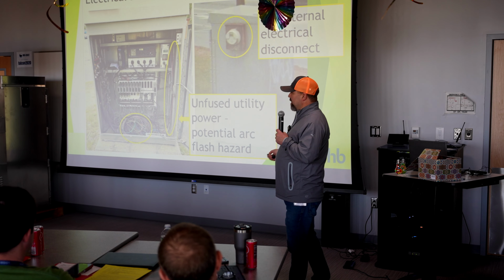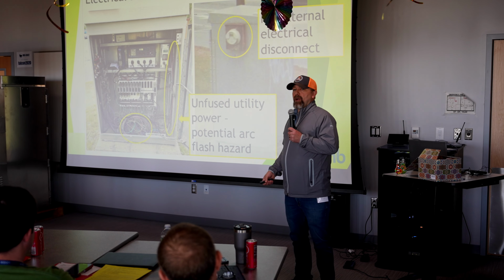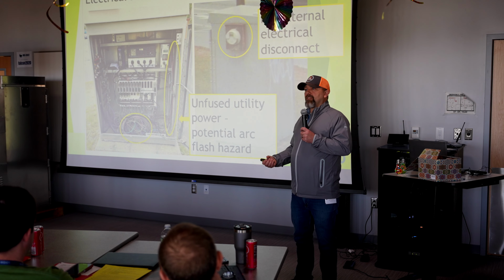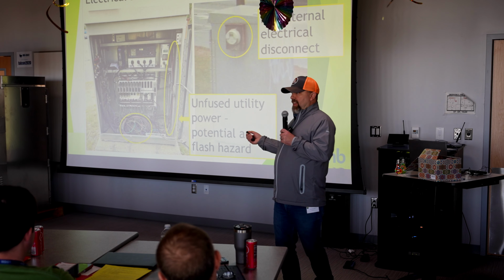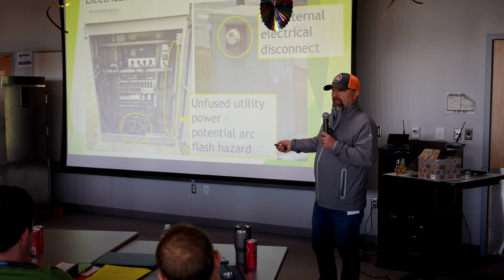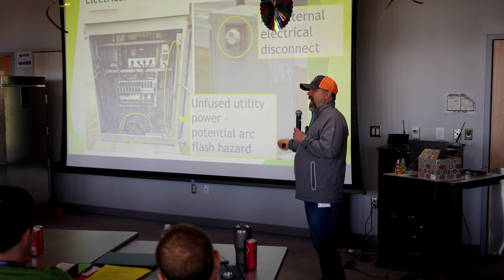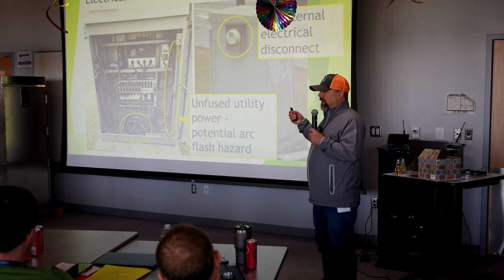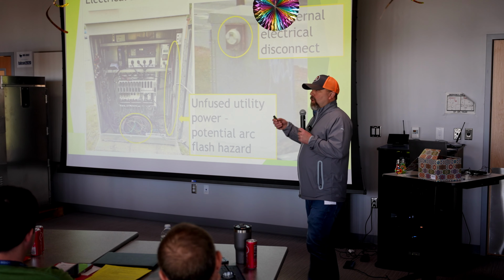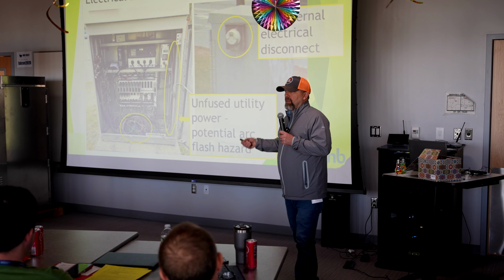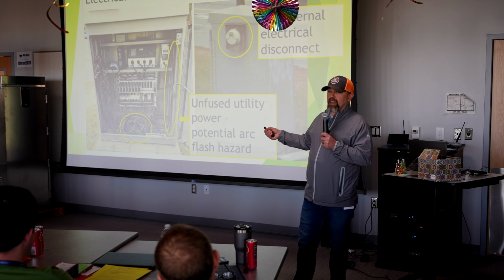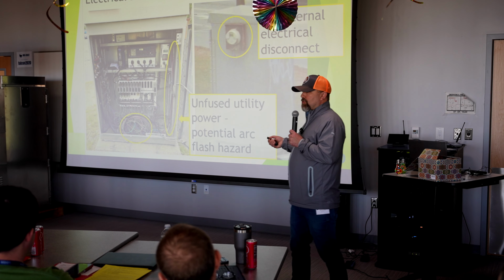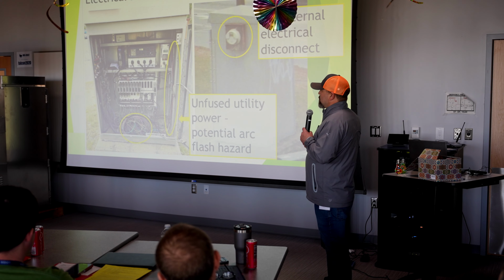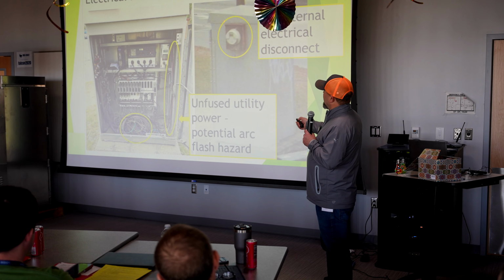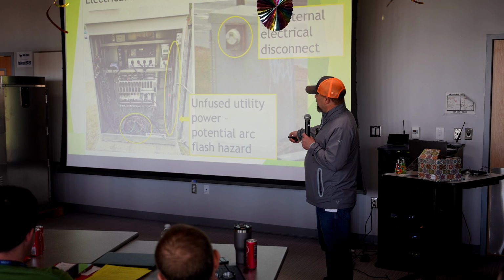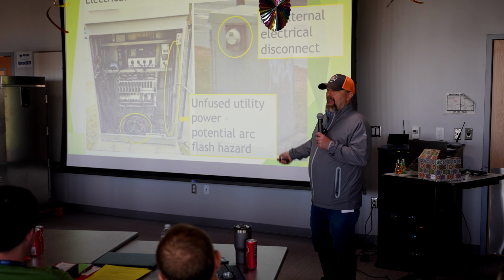So what you're dealing with is unfused utility power. When we start talking arc flash potential, that's your most likely culprit for there to actually be an accident, where you have a chafed wire or a wire gets pinched in the door. You're actually going to have a lot of potential energy coming from the transformer, because there's no service disconnect until it comes back out of the meter and down to the main breaker in the cabinet.